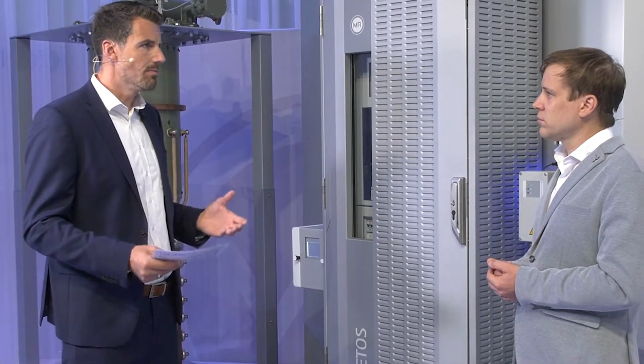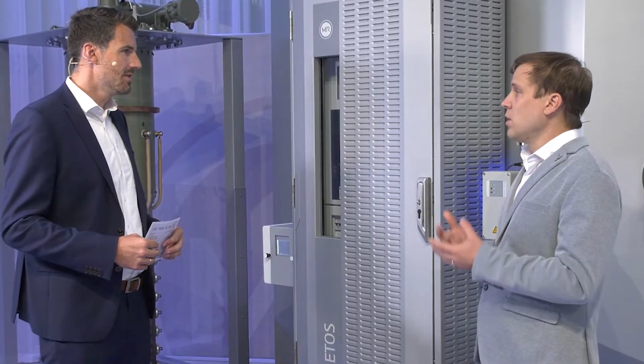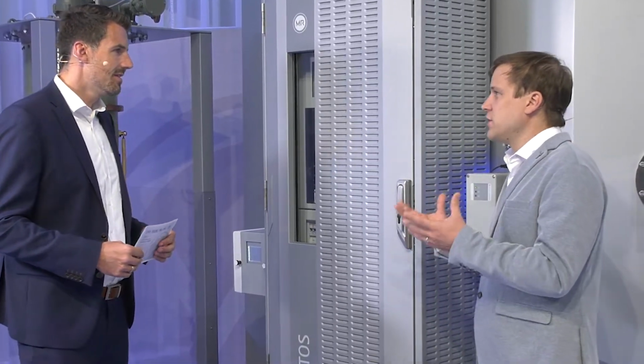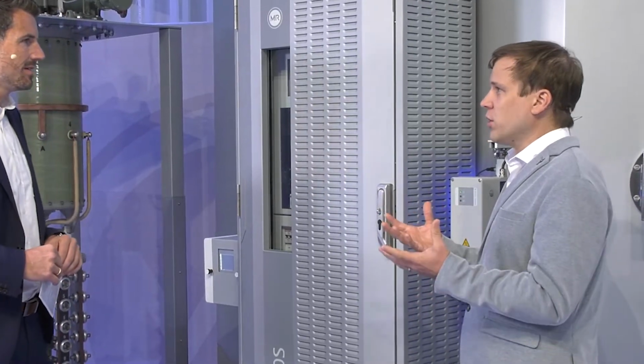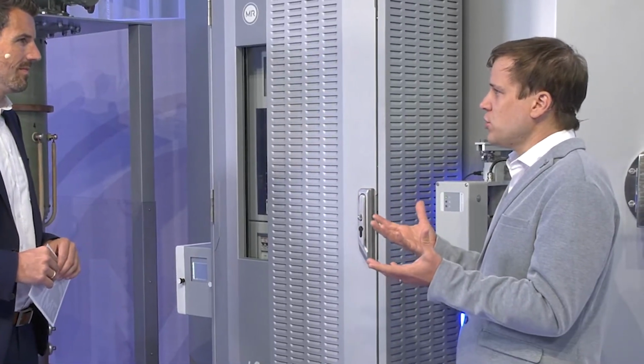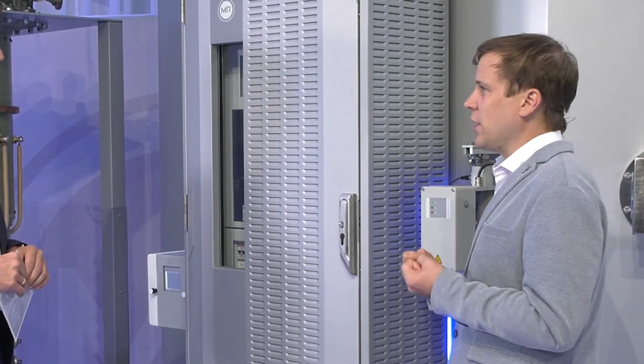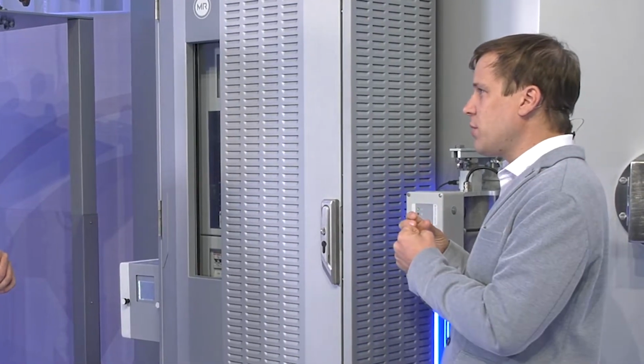Okay, talking about a very important technical parameter, temperature. What options do we have available at MR in terms of supporting monitoring the temperature on the power transformers? Well, if we talk about temperature, the hotspot is the interesting point, obviously. For the hotspot, we have two classical solutions. The one would be the calculation of the hotspot. Therefore, we only need a top oil temperature and the load current of the transformer. Some more factors are required for that. It's based on different standards, but then we can calculate the temperature. But that's still just a calculation.